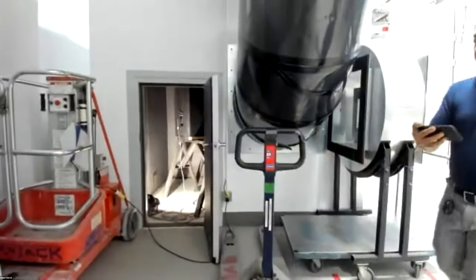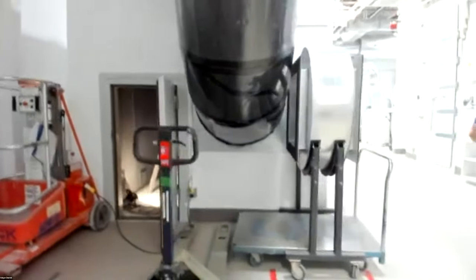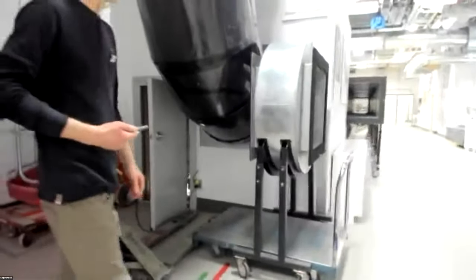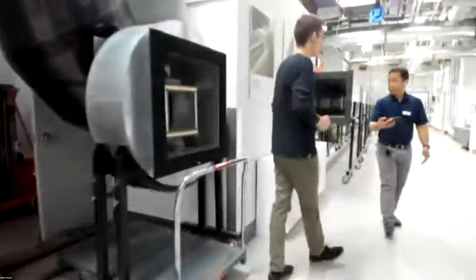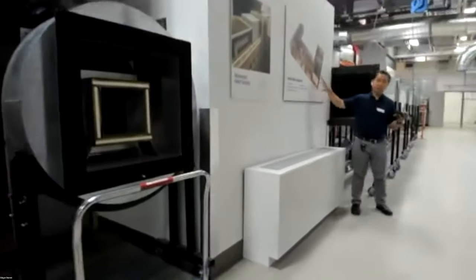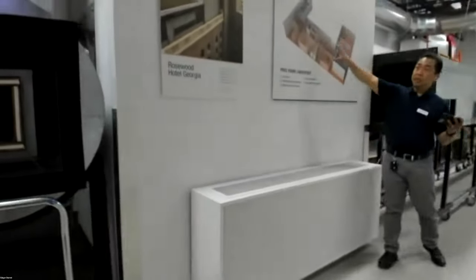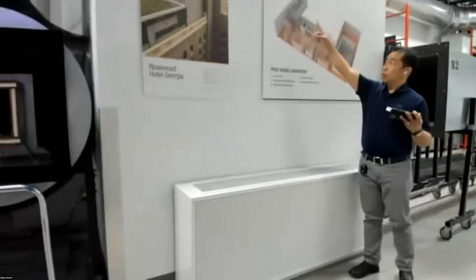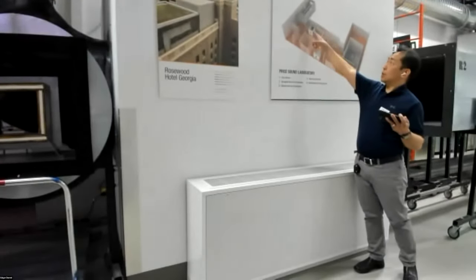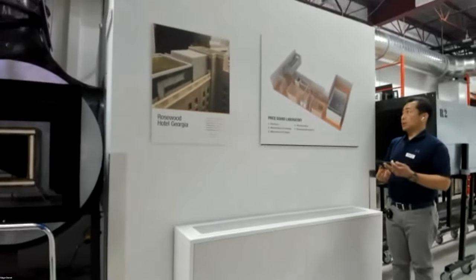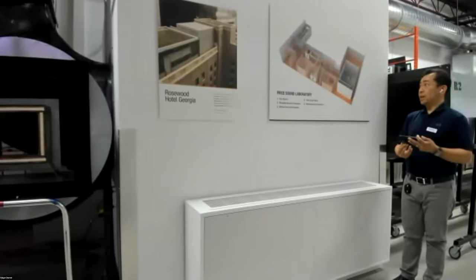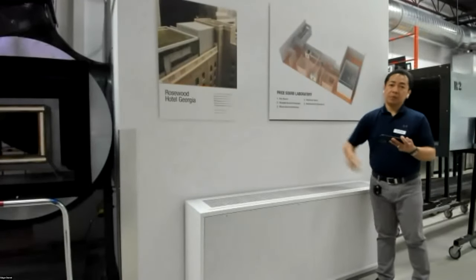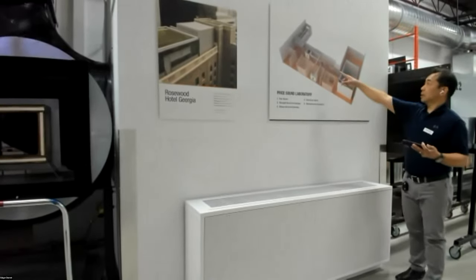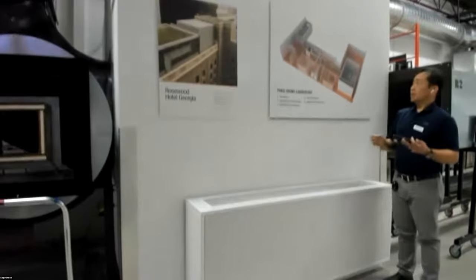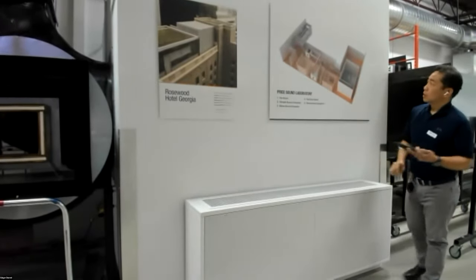And here we're going to the next station, which is the duct system. But before we go to the next station, I would like to mention the slide here. We have the four-part system. One is the fan room that supplies air, and then we have the source chamber that mimics the sound generated by any equipment or anything that we need to silence. And then we have also the elbow source chamber for testing elbow silencers, and the duct system, that's where we test the silencer, and the reverberation room. So next we go to the duct system, how we test the silencer.